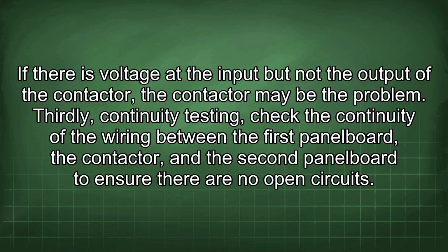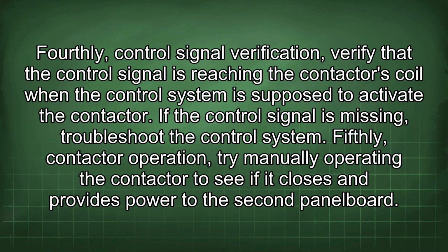Thirdly, continuity testing. Check the continuity of the wiring between the first panel board, the contactor, and the second panel board to ensure there are no open circuits. Fourthly, control signal verification. Verify that the control signal is reaching the contactor's coil when the control system is supposed to activate the contactor. If the control signal is missing, troubleshoot the control system.